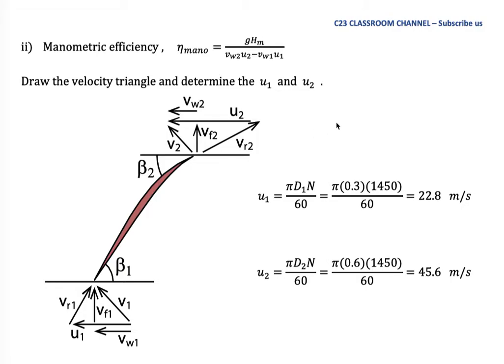The first parameter calculated by fixed equation is u, the tangential velocity. The basic equation is u = πDN/60. Since we have inlet and outlet: U1 = πD1·N/60 and U2 = πD2·N/60. The unit for u is meters per second and N is in rotations per minute, so we divide by 60. Substituting values: U1 = 22.8 m/s and U2 = 45.6 m/s.